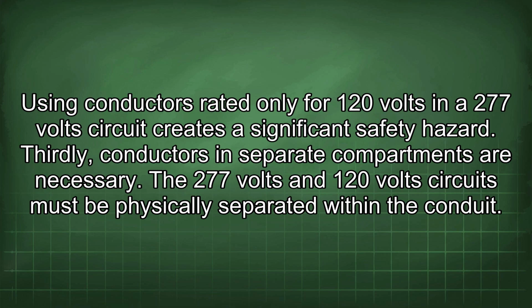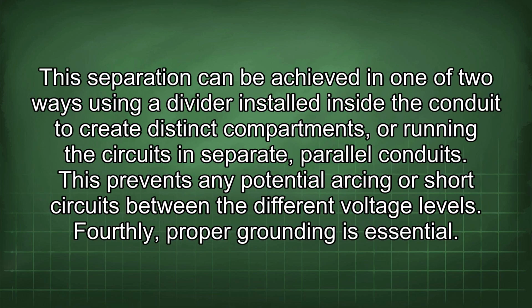The 277 volt and 120 volt circuits must be physically separated within the conduit. This separation can be achieved in one of two ways: using a divider installed inside the conduit to create distinct compartments, or running the circuits in separate parallel conduits. This prevents any potential arcing or short circuits between the different voltage levels.